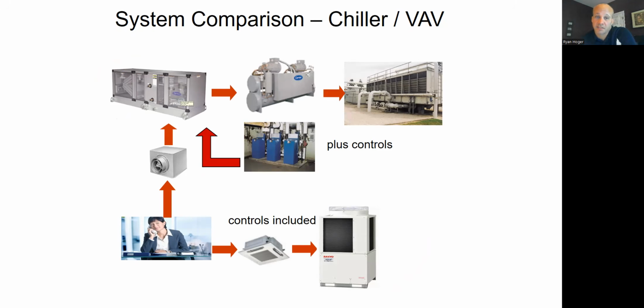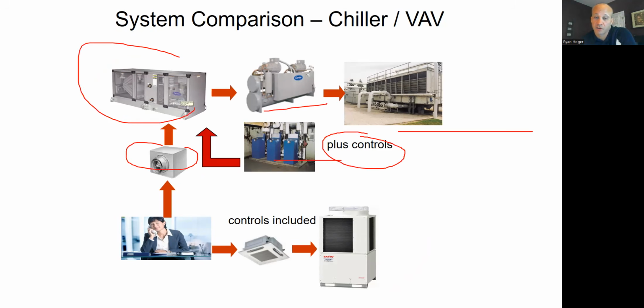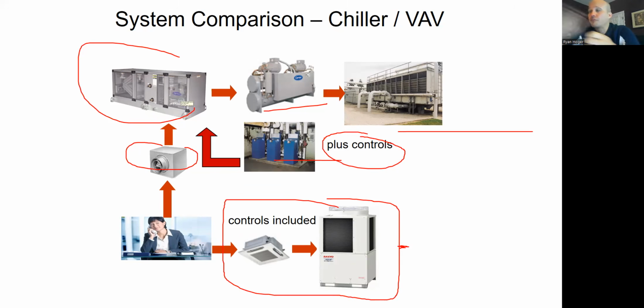If I have more complicated systems, in this case, chiller plant, boiler plant, cooling tower, all those VAV boxes, all those air handlers, and the controls to make all that work versus this prepackaged VRF system, this guy can win a lot of times. You won't do it on every job. Once again, if you already own a chiller and a boiler and a piping system and fan coils and air handlers, you're probably just going to keep that. But if you don't have any of that infrastructure, you may choose to do VRF.